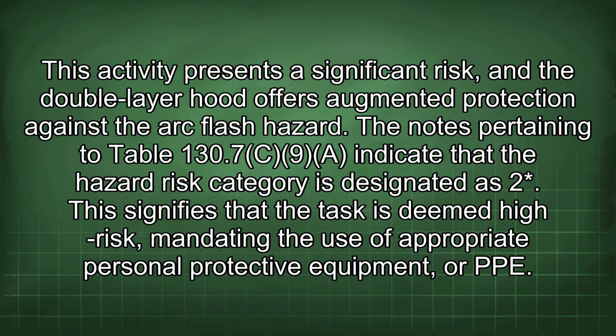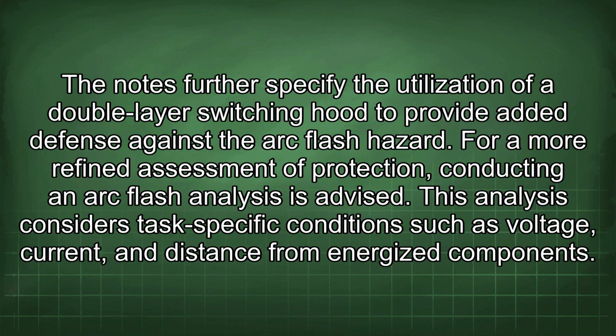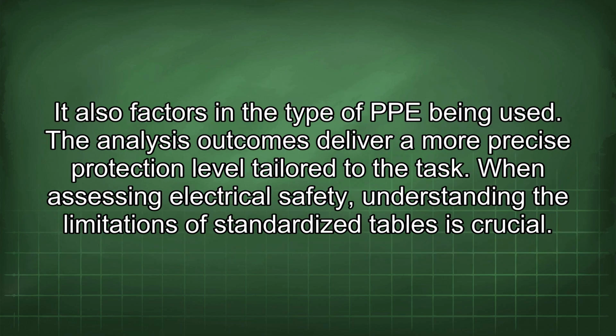The notes pertaining to Table 130.7c9 indicate that the hazard risk category is designated as 2*. This signifies that the task is deemed high risk, mandating the use of appropriate personal protective equipment, or PPE. The notes further specify the utilization of a double-layer switching hood to provide added defense against the arc flash hazard. For a more refined assessment of protection, conducting an arc flash analysis is advised. This analysis considers task-specific conditions such as voltage, current, and distance from energized components. It also factors in the type of PPE being used. The analysis outcomes deliver a more precise protection level tailored to the task.